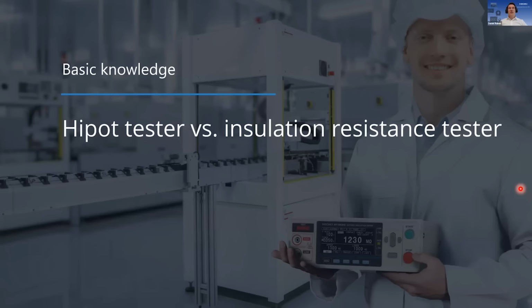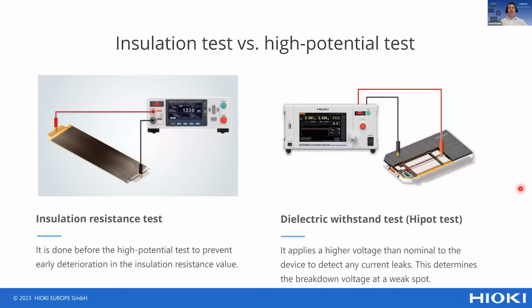As a start, the basic knowledge, what the HiPot tester is doing compared to an insulation resistance tester. So as you can see here on the screen, we have the insulation resistance test versus the withstand test, also so-called HiPot test, which is basically a safety test. As you can see here on the application already, we have here a cell, while the safety test is being done with the pack or the module.